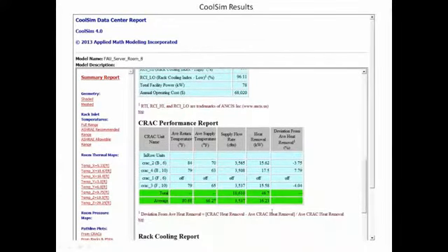And if we take a look at the CRAC performance report, we can see part of the reason that is the case. Remember that these units should be delivering a delta T of 20 as well, and you can see they are not. They're ranging 14. Here I've got 16, 14 delta T, so those are low. The flow rates are shown here. These are actuals, and we have one unit that shut off, and it was shut off when we did these measurements, and so we wanted to calibrate the model, of course, by shutting it off in the model.